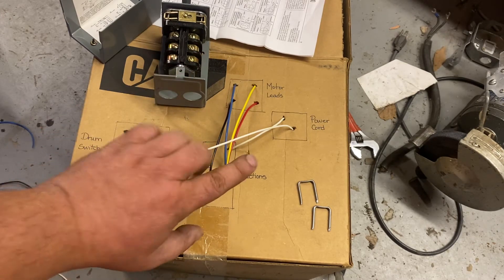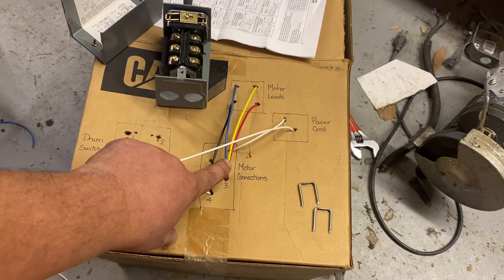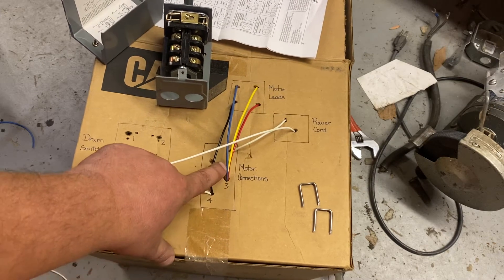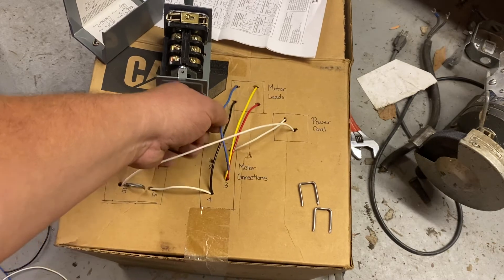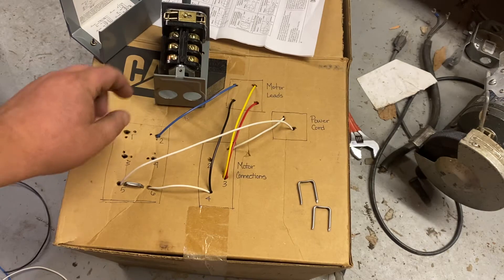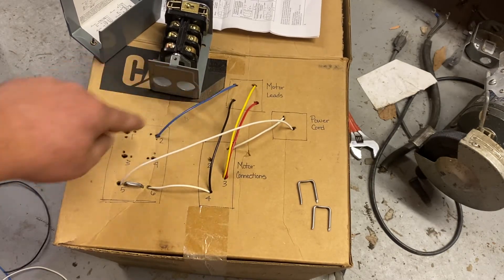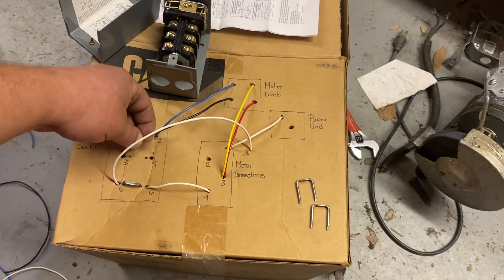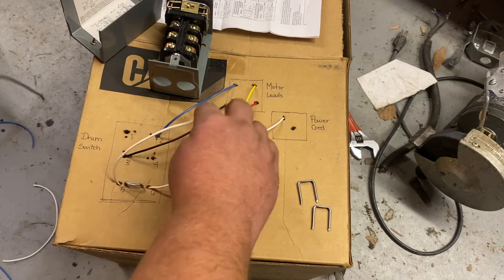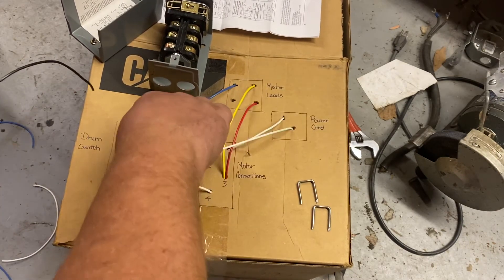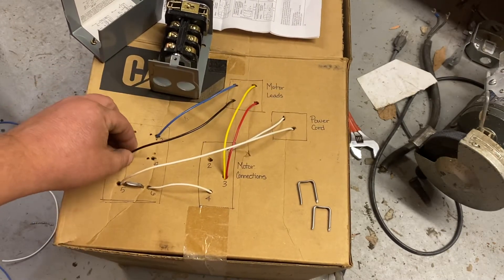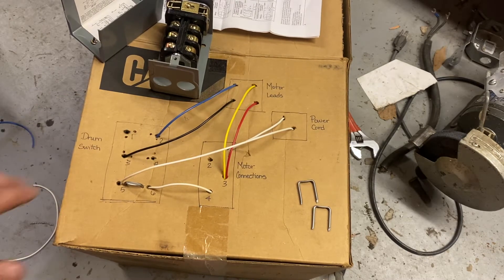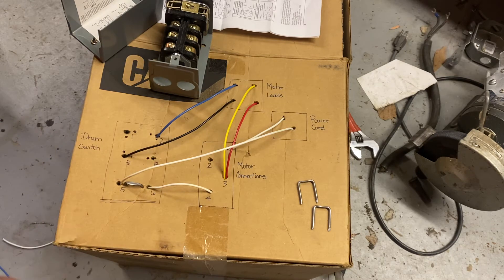Now, just hooking it up like this, it'll run in forward. But for this particular motor, we need to swap four and three to make it go. So what we do is you run four over to the switch. Okay, so now it's going to go through the switch before it goes to the motor. And with this guy, it's going to go here to three.